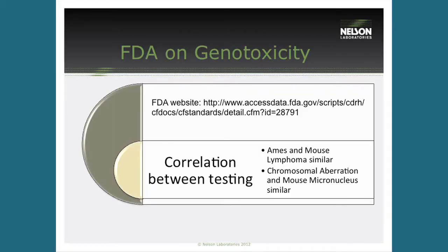As we stand right now, this is the guidance document. The new ISO 10993-3 will actually incorporate this — we're adopting in ISO 10993 the idea of doing an Ames test, then either the mouse lymphoma or chromosome aberration, and then the mouse micronucleus test. The new ISO will fall in line with the FDA guidance. That means that even if you're submitting to Europe now and might not have to do the mouse micronucleus, to be compliant with the new ISO when it's released, the mouse micronucleus test should be evaluated.